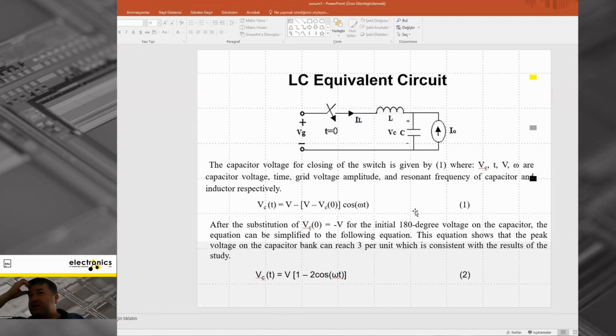We closed the breaker at 180 degree. Why? Because we want to see the worst transient voltage. So when we close the breaker at 180 degree, we produce the worst transient voltage. This equation shows that the peak voltage on the capacitor bank reaches 3 per unit, which is consistent with the result of the study.